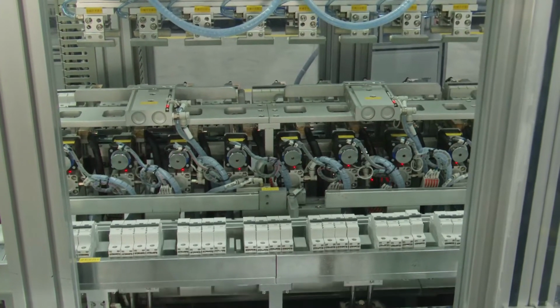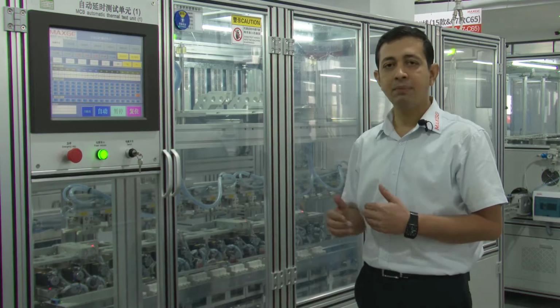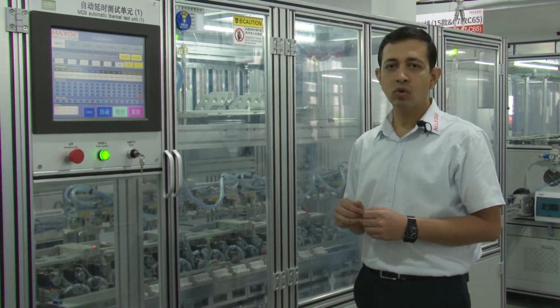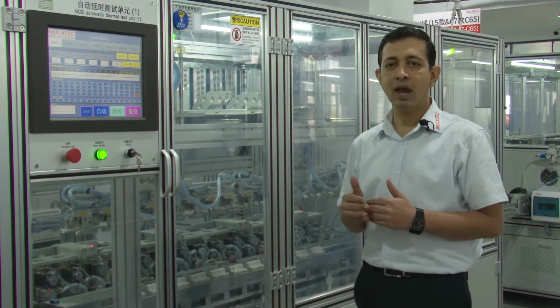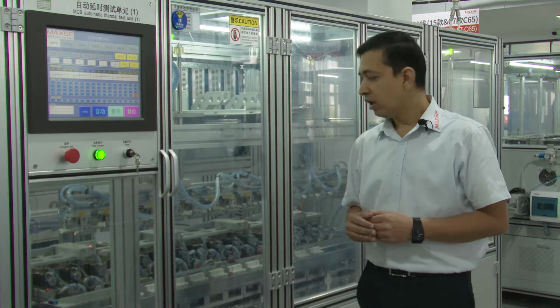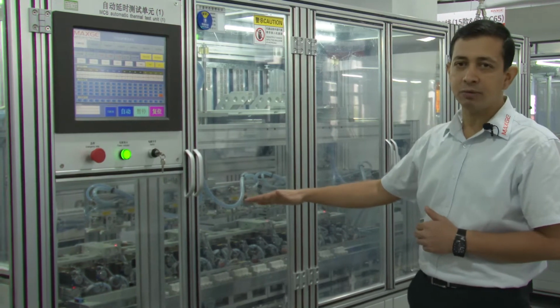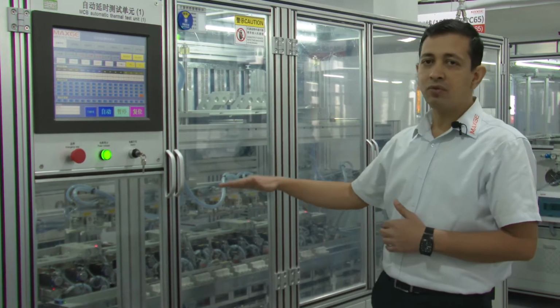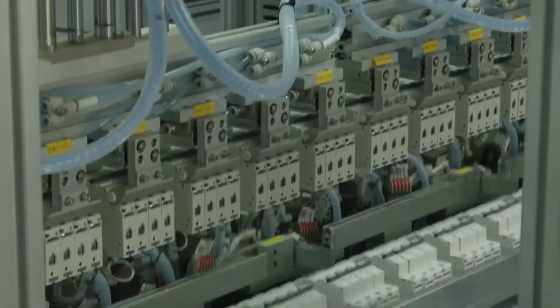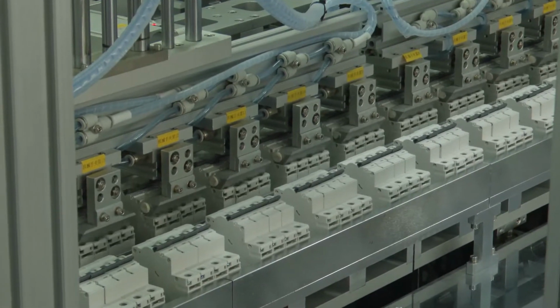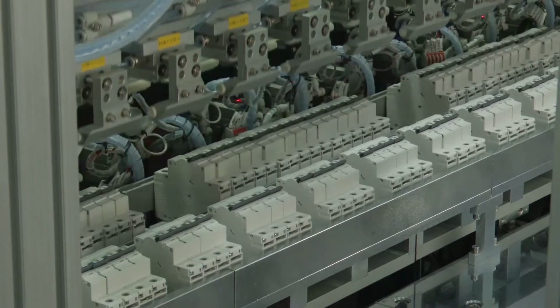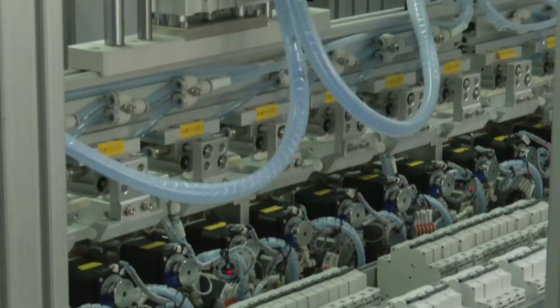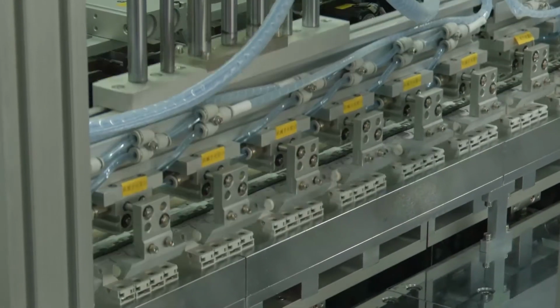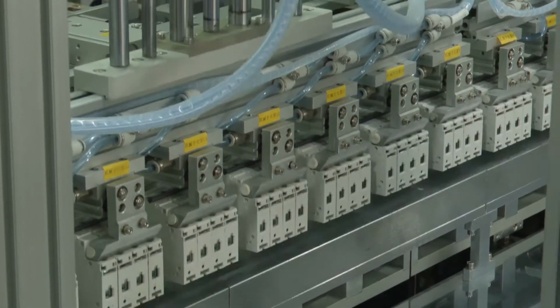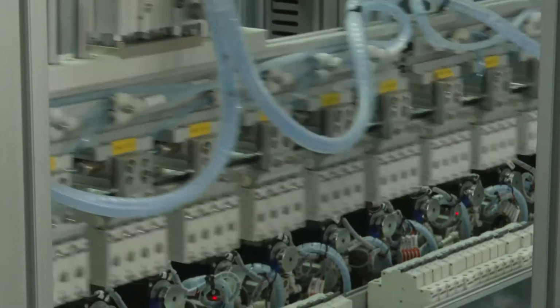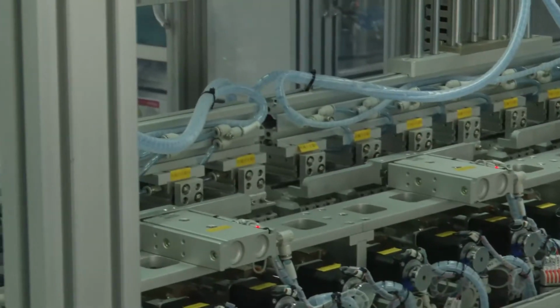During the hot calibration we pass the current, and at the same time we rotate the screw to adjust the calibration gap between the bimetal and the tripping lever. This is done automatically by this machine. With the hot calibration we can ensure that the thermal tripping is within the range, and with this the overload tripping, as mentioned in the IEC 60898 standard, passes at 1.13 In to 1.45 In.